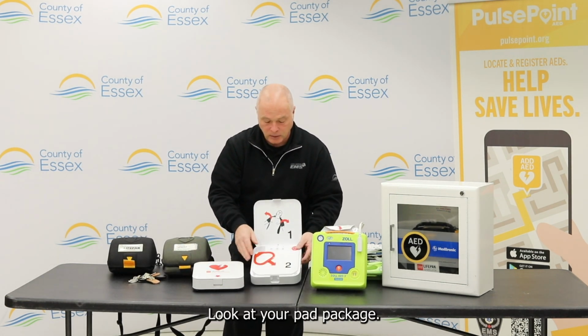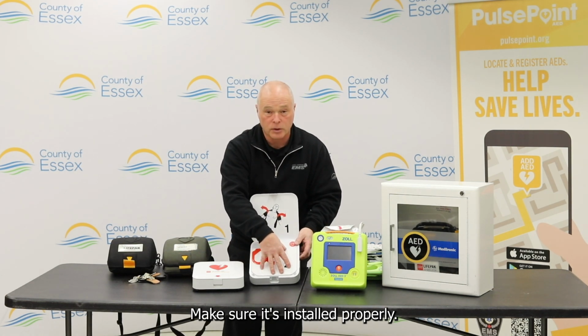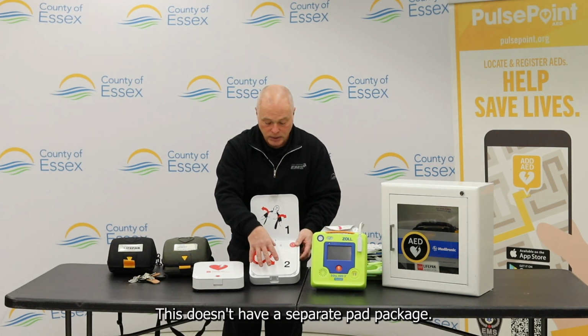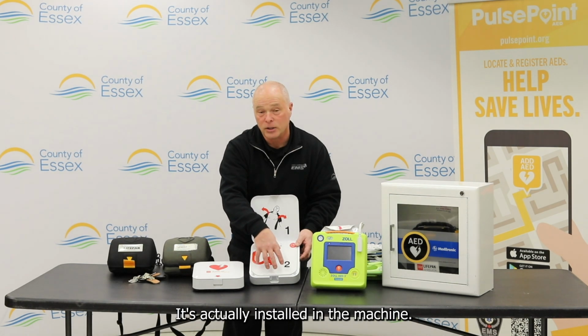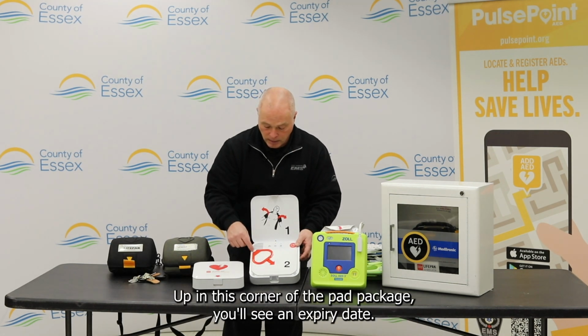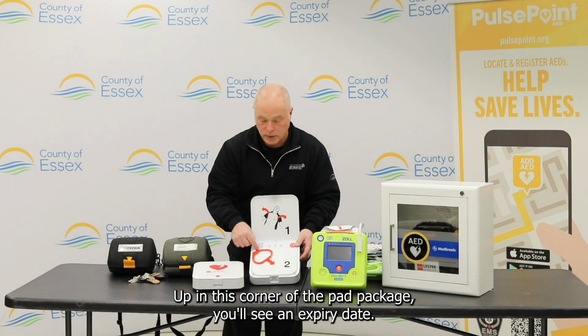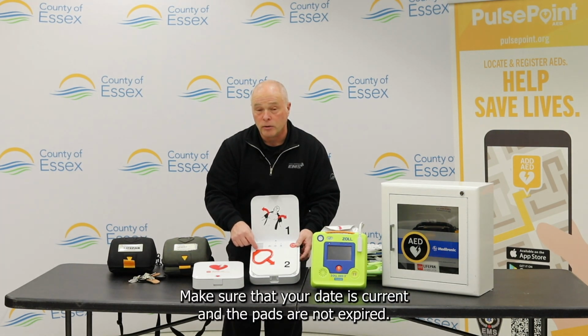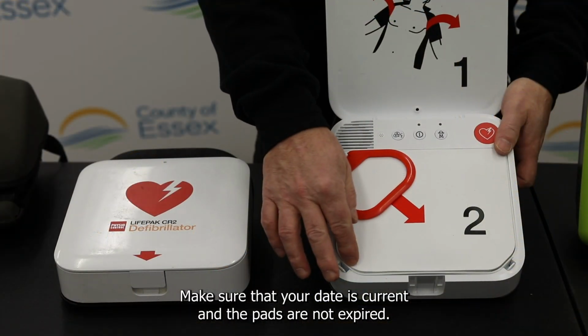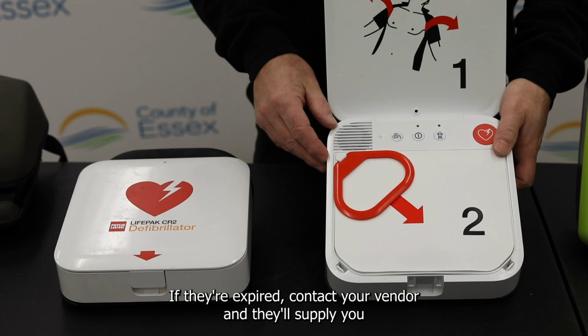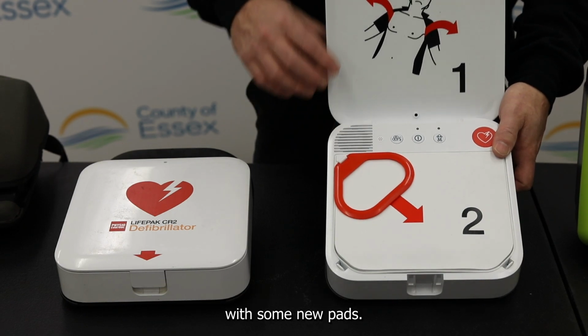Open the lid, look at your pad package, make sure it's installed properly. This doesn't have a separate pad package, it's actually installed in the machine. Up in this corner of the pad package, you'll see an expiry date. Make sure that your date is current and the pads are not expired. If they're expired, contact your vendor and they'll supply you with some new pads.